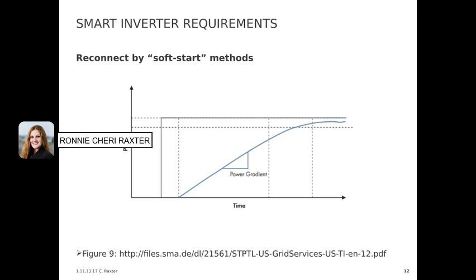The next setting is reconnect by soft start methods. Like the majority of the other settings, this one has to be activated. In the event of a grid failure, this function requires the DERs to wait a predetermined amount of time before they're allowed to reconnect. On top of that, they're only allowed to reconnect incrementally. Whereas previously, like when the sun comes up and hits the modules and the PV inverters start producing as much power as they can, this is similar to that. It only allows them to turn on incrementally to allow the grid to stabilize before slowly ramping up. And this is to prevent rapid changes from PV on the utility grid.